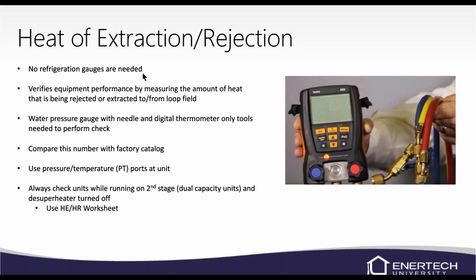Well, you'll need a water pressure gauge with a needle to insert into the pressure temperature ports. You'll need a digital thermometer and also the specs from the IOM. Make sure you always install pressure temperature ports. If you've got a water-to-water unit, make sure you install them on the load and the source.